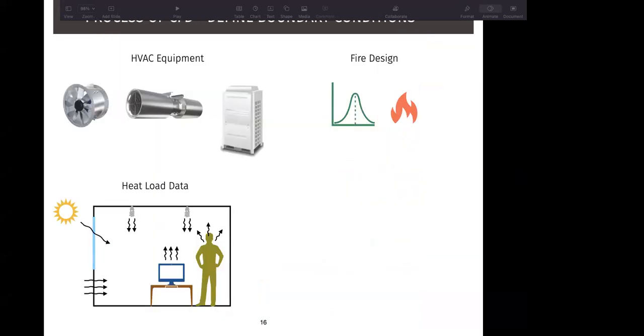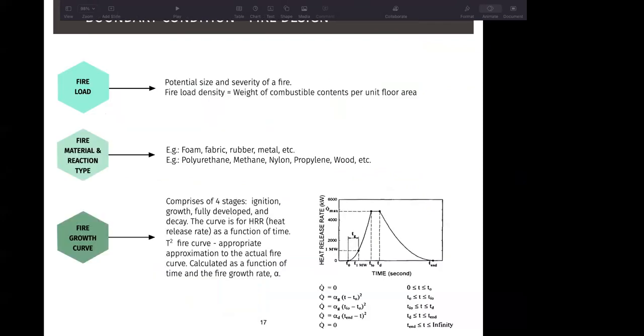The third kind of boundary condition could be a fire design. So in case you're studying fire load and smoke movement, fire design then becomes the third kind of boundary condition you can apply to the system. What we mean by fire design is the fire load, that is the intensity of fire, the fire material. So what kind of material is on fire, that would dictate the amount of soot being created, the amount of peak heat, peak fire load being considered, and the fire growth curve, which is in 4 stages: the ignition, the growth, fully developed stage, and decay. This fire growth curve works as a function of time. It is approximated as a t-square time curve, fire curve, and the 4 stages are followed for any given item on fire.